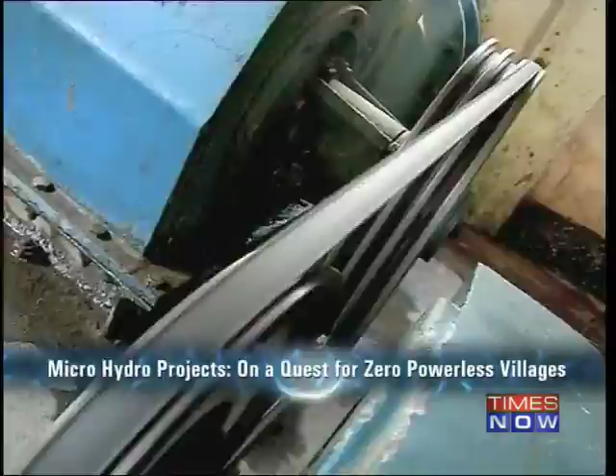Number two is to allow extra water to flow out and go back to the river. Number three is to allow all the silt and sand still flowing in the water to settle there. Number four is to stop all leaves and wood flowing into the channel, stopped at the trash rack. And number five is to allow easy flow of water into the pipeline that ultimately reaches the turbine.